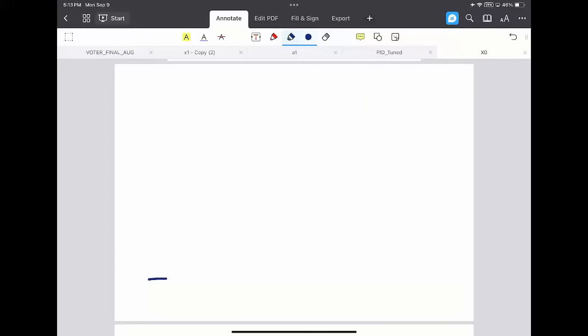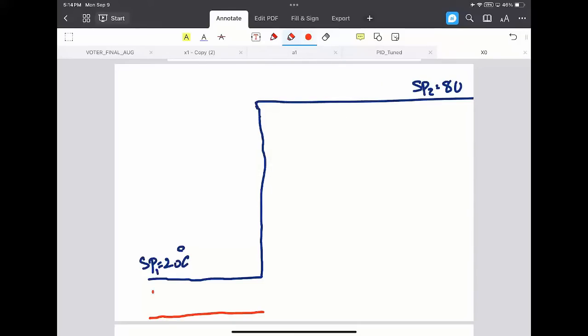We have the set value of 20 during the startup. It's okay during the startup of a machine. The machine is in cool-down, ambient temperature of 20 centigrade. And we want to heat, warm up the machine and reach to setpoint 2 of 80. So in this case, we may start with zero in control value, the output of valve. I just use the Siemens notation here, LMN or CV of 0% here.